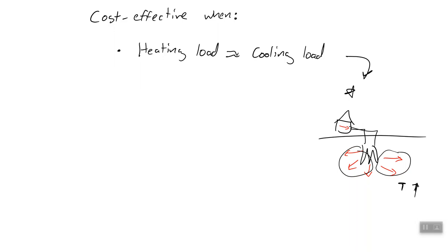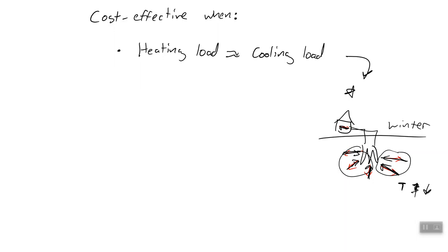In a more temperate climate, say Ohio, then in the wintertime, all of these arrows would be switched, and you would then cool the ground, right? As you reject heat from the ground into your building, that causes the temperature of the ground to go down. But if the amount of heat you pull out of the ground is much less than the amount you need to cool, then the temperature of the ground will actually continuously increase, and can increase rapidly if you're only cooling and never heating.